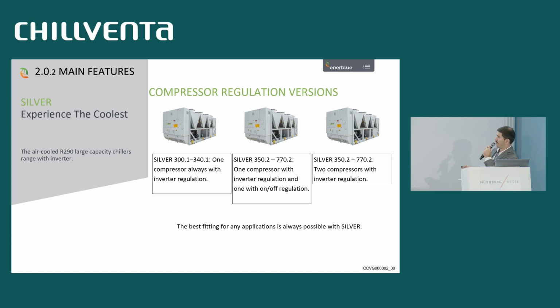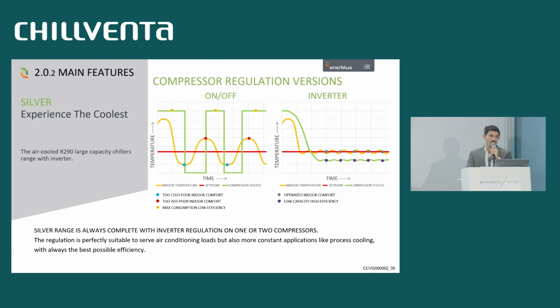The following sizes go from size 350 to 770. In this case, it is possible to choose one inverter-driven compressor and one on-off compressor. Alternatively, we can have two inverter-driven compressors, which is much more suggested in case we have air conditioning application, because the set point is much more regular and the efficiency of the unit is much, much higher. If we have industrial applications, so process cooling applications, also concerning the norm, on-off compressors are tolerated. Of course, the reaching of the set point is not as stable as with twin inverter, but in any case, we expect the process cooling to be more constant than air conditioning applications.